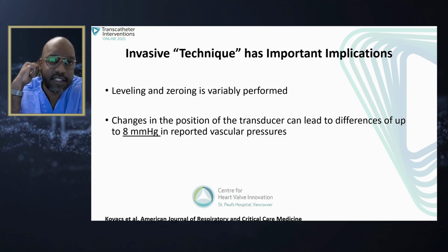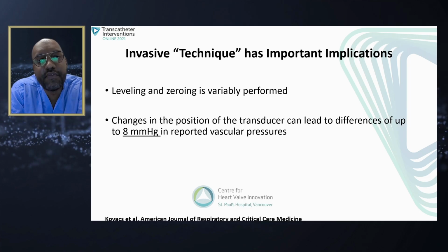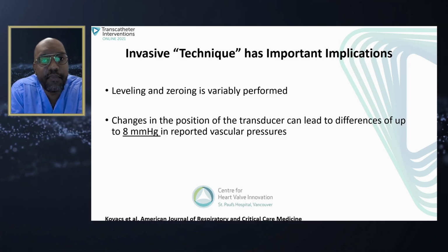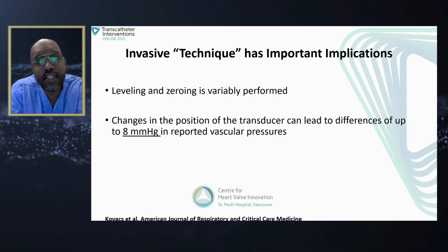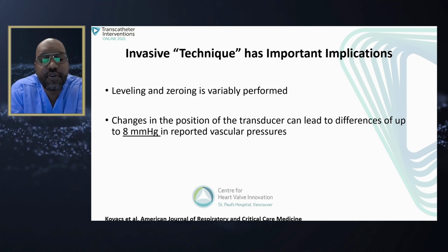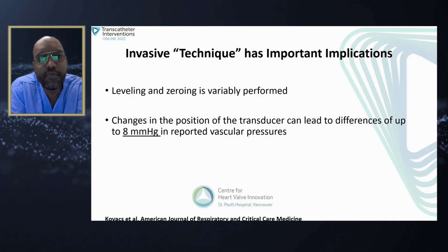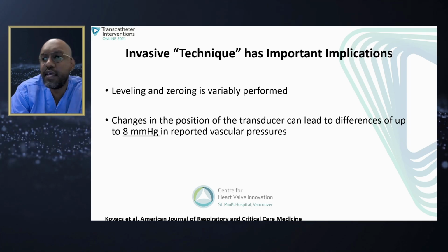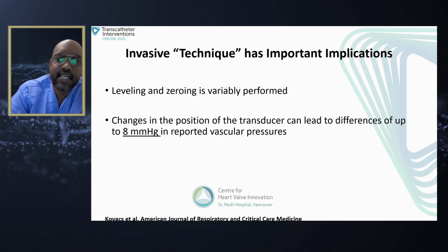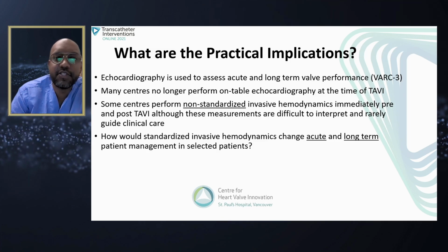So what we've seen locally, and what David will highlight from some of the sites from the discordance TAVR study, is that we really had to evaluate our own approach to how we do this technique. It's become clear, and when you look at your own labs, I'm sure we would all admit that how leveling and zeroing is done is performed variably. Quality maybe is an issue, and we know that even just changes in technique can impact the values by as much as 8 or more, and that's been shown.